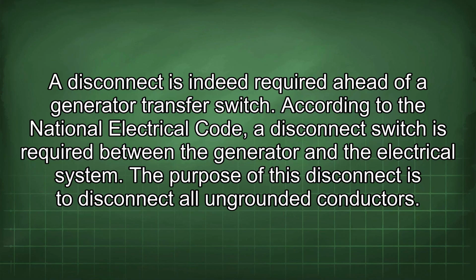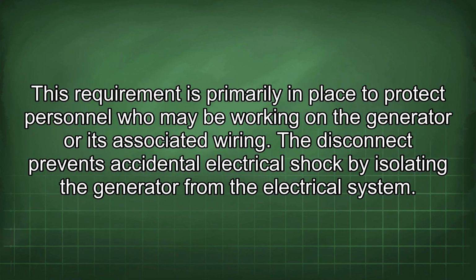A disconnect is indeed required ahead of a generator transfer switch. According to the National Electrical Code, a disconnect switch is required between the generator and the electrical system. The purpose of this disconnect is to disconnect all ungrounded conductors. This requirement is primarily in place to protect personnel who may be working on the generator or its associated wiring.